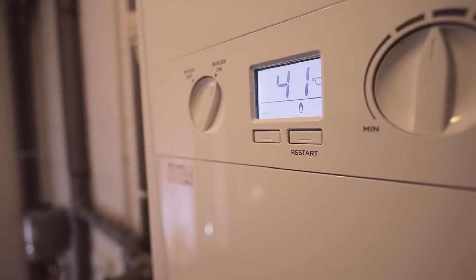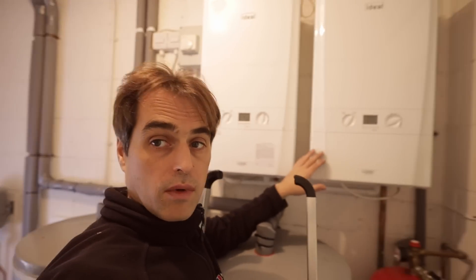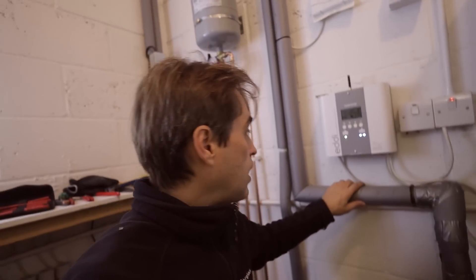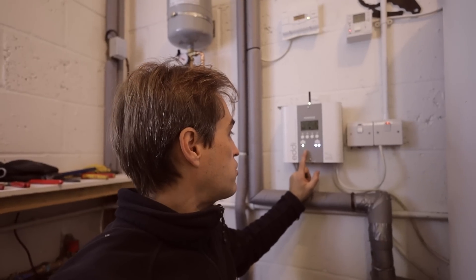With 12 degrees outside I've got the boiler running at 40 degrees C — those temperatures are well over 90% efficient on central heating. This other boiler will only kick in for about 40 minutes a day to recharge the cylinder, if it has to kick in at all, because we've got 7 kilowatts of solar PV on the roof and an Eddy solar diverter that's right now charging the cylinder. I'm going to set the gas boiler on this programmer to only kick in in the late afternoon for about an hour, and on a nice sunny day that boiler won't kick in at all.